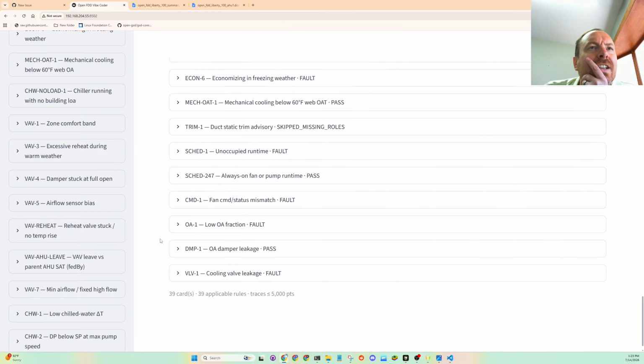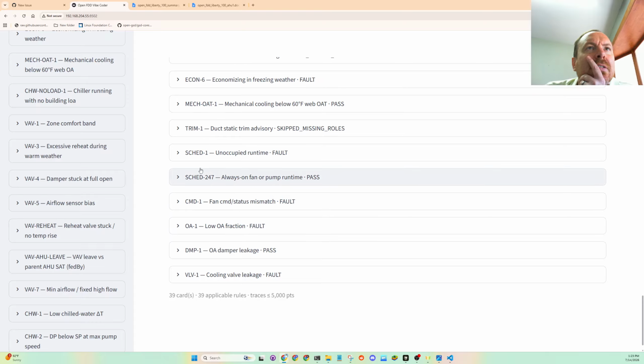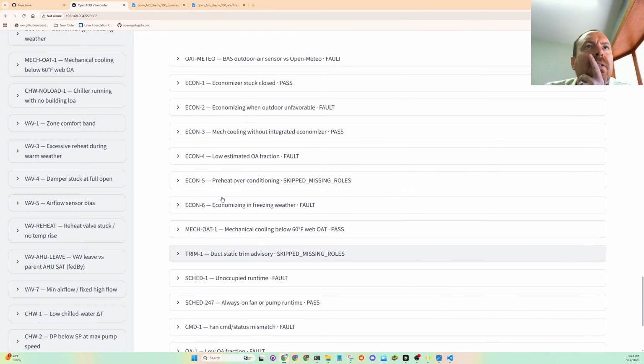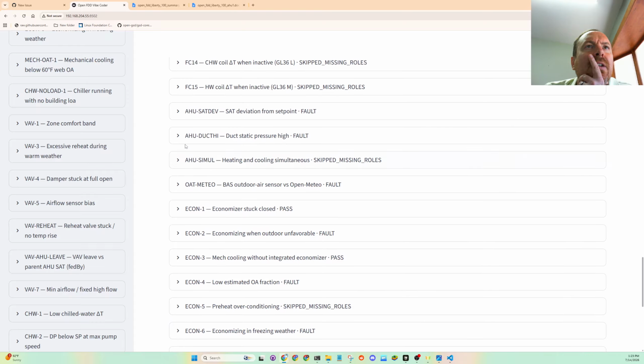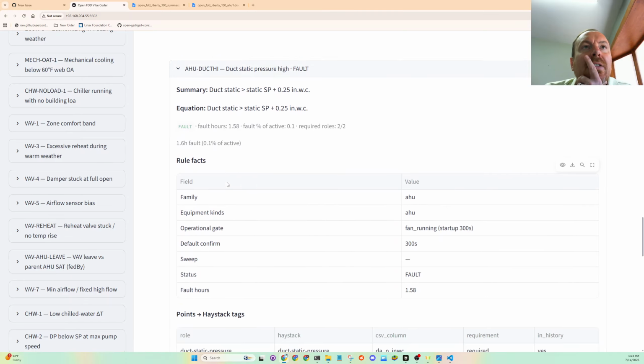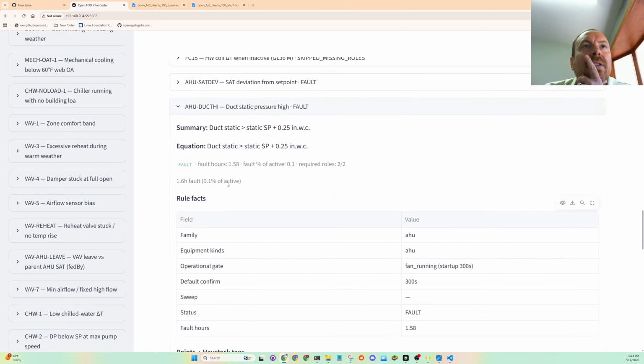We should have a... What is this? Duct static high fault. So let's just look at this one. So this is duct static high. Let's see how many fault hours this is.